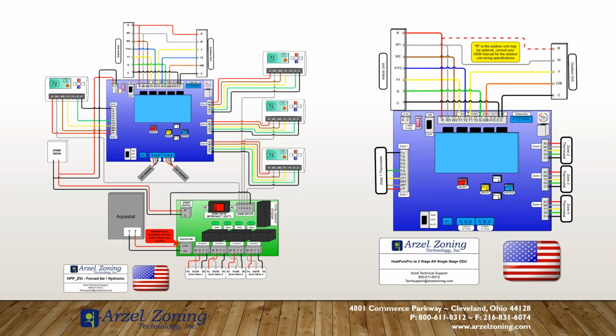With the Heat Pump Pro, extremely simple. Call for Heat W, gives you all your electric control. So 4 stages of heat, 2 stages of cooling, or if you have dual fuel, it gives you that dual fuel changeover based on outdoor air temperature. But the Heat Pump Pro is your universal panel, good for anything single stage conventional all the way up through 2-stage dual fuel. Now there are custom applications where we have an accessory control. We call it a ZVI, a zone valve interface. That ZVI control allows us to add boiler heat with forced air heat very easily.